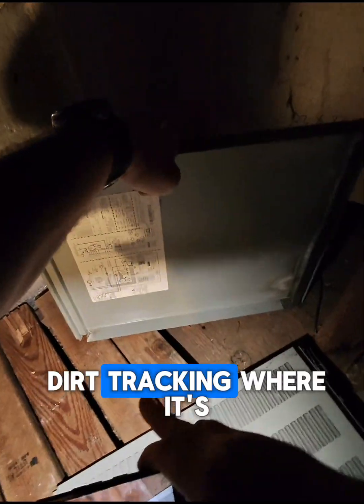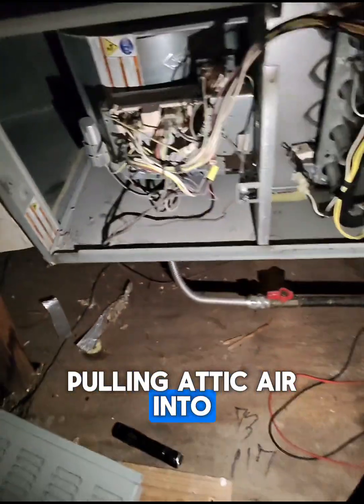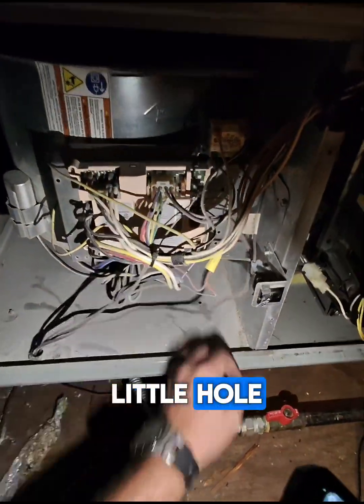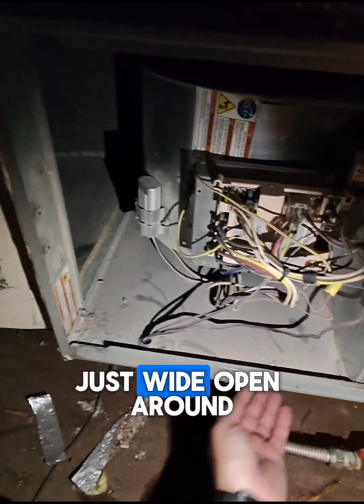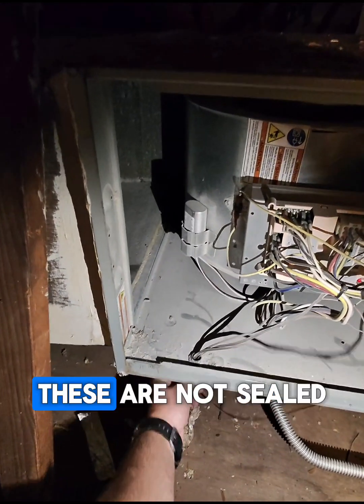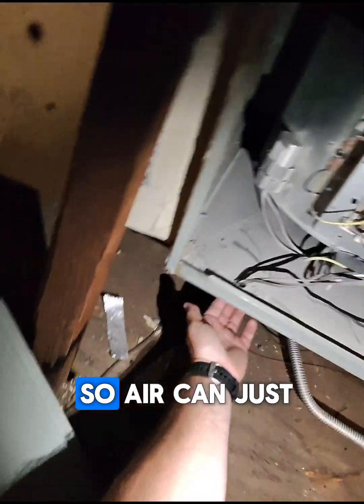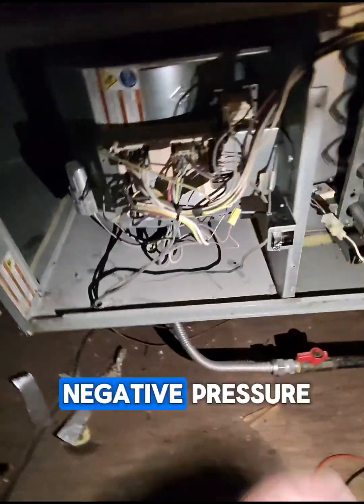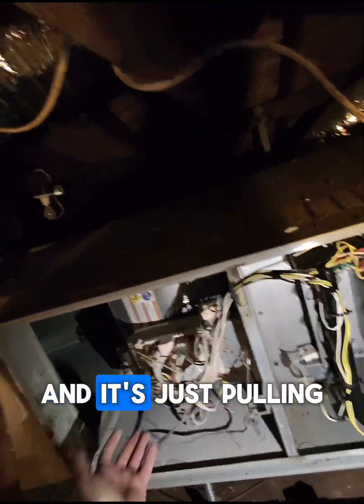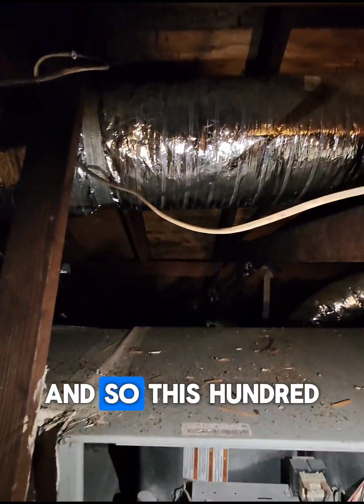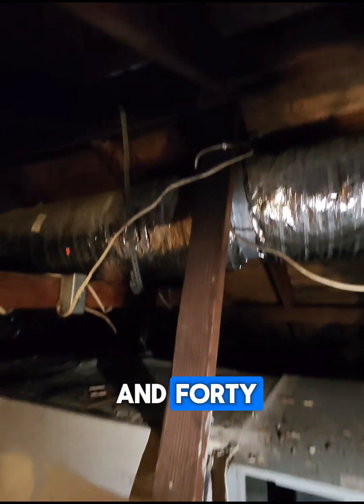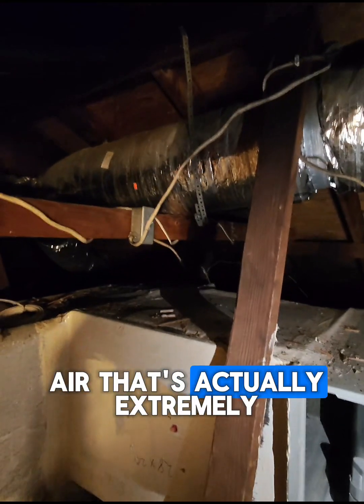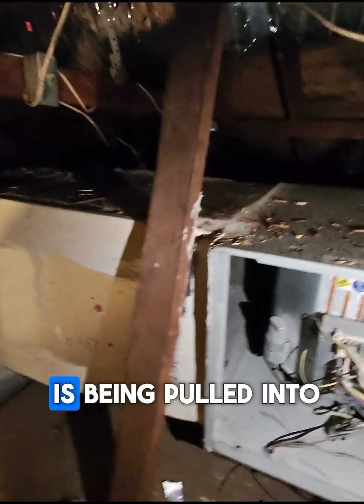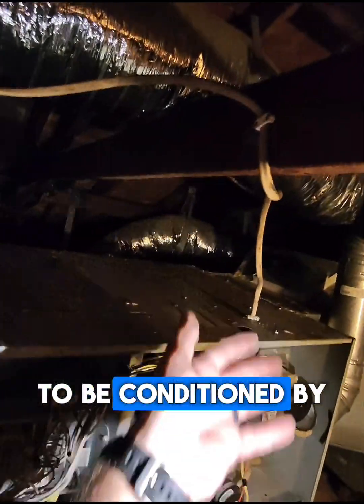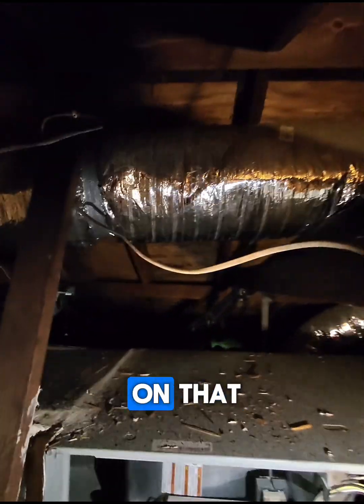You can see that dirt tracking where it's pulling attic air in too. And even on the inside of here, look, we've got a little hole just wide open around your electrical connections too. These are not sealed, so air can just travel right in there. This is under a negative pressure, so it's got a vacuum in there and it's just pulling air in around all these little spots. And so this 140, 160 degree air that's actually extremely humid too, because we're in Houston, is being pulled into your system to be conditioned by your air conditioner, and you're wasting capacity on that.